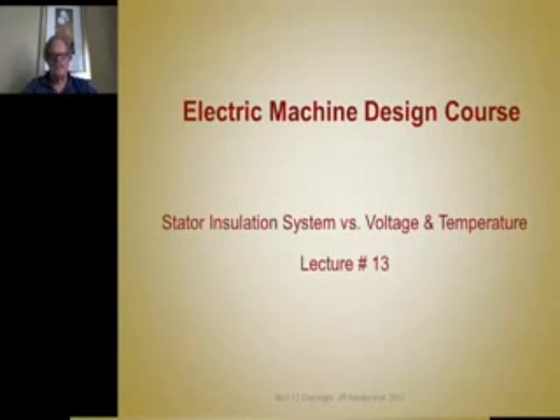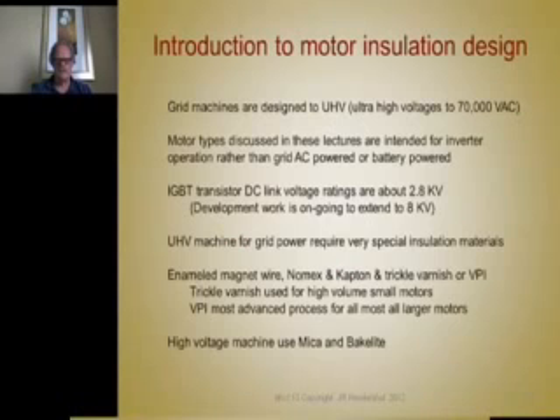This lecture covers the insulation systems that are required for the stator phase windings for these three machines, and the level of insulation is based on the operating temperature requirements and the voltage requirements.